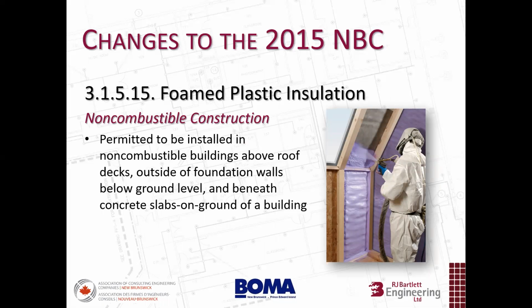So for non-combustible construction, foam plastic is a little bit more limited as to where you can use it, and there are some thermal barrier requirements. It's permitted to be installed in non-combustible buildings above roof decks, outside of foundation walls, and below ground level beneath concrete slabs on ground of the building. So that's basically permitted to be outside of the building envelope, as opposed to within the walls and interior walls.